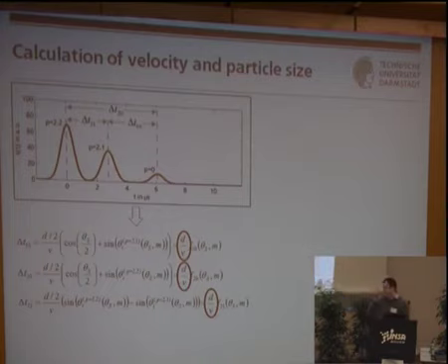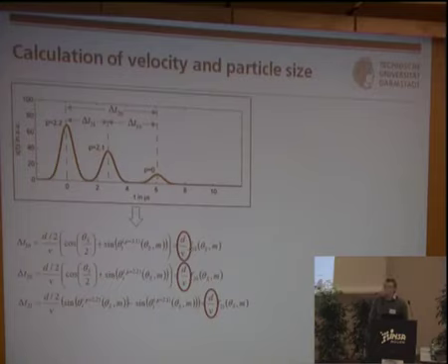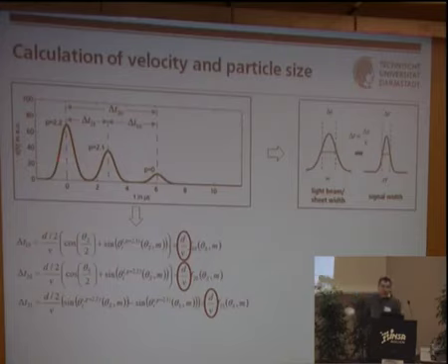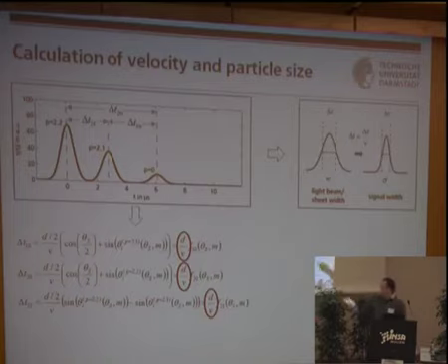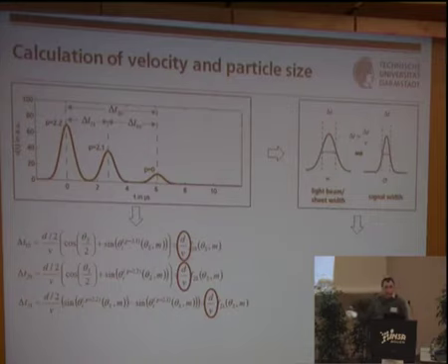If you want to use this time distance to calculate the particle size, you must know the velocity. We also calculate the velocity from the time shift technique, taking advantage of the fact that the width of the individual peak is related to the beam shape, to the size of the light beam, and to the velocity. It means we can use this simple relation to calculate velocity.